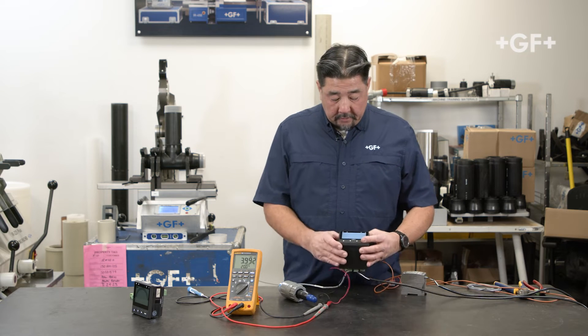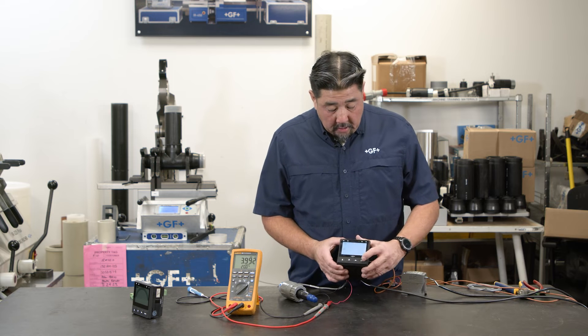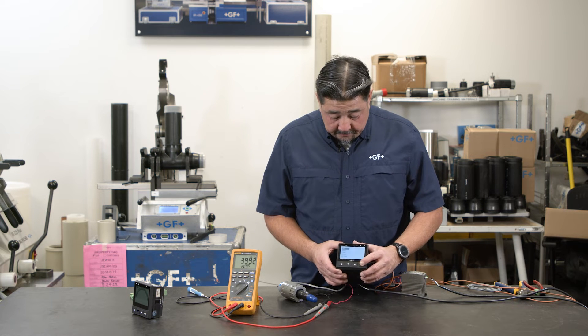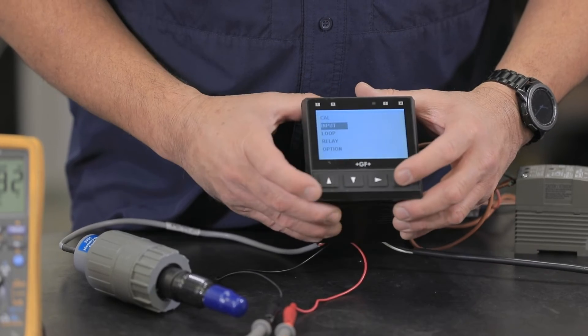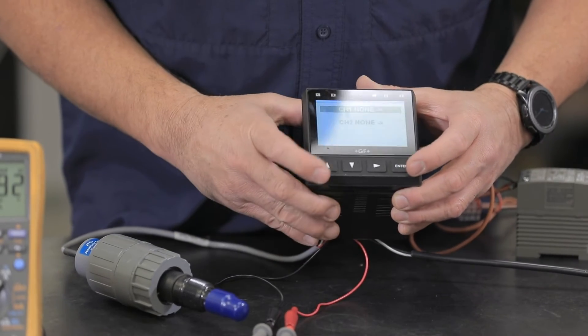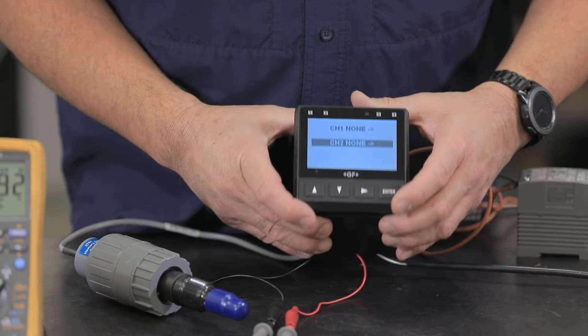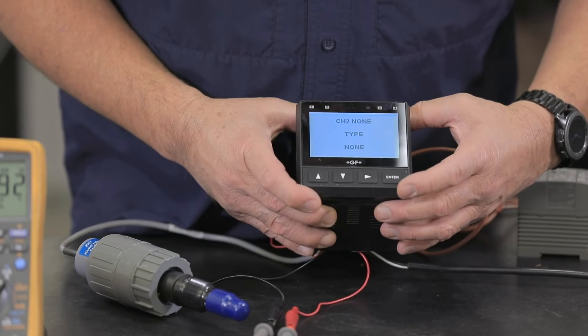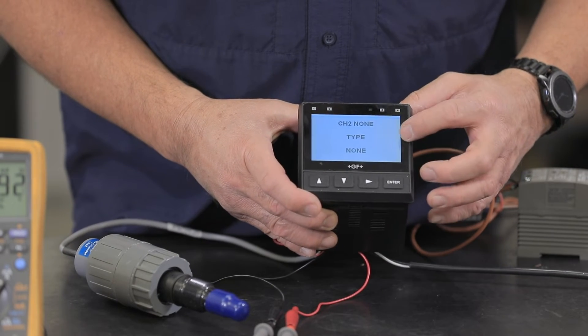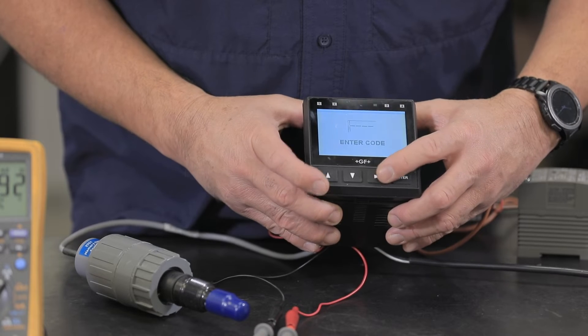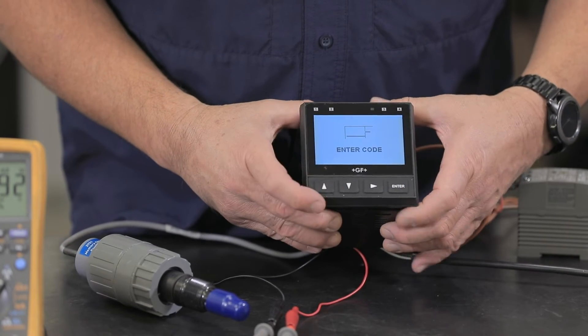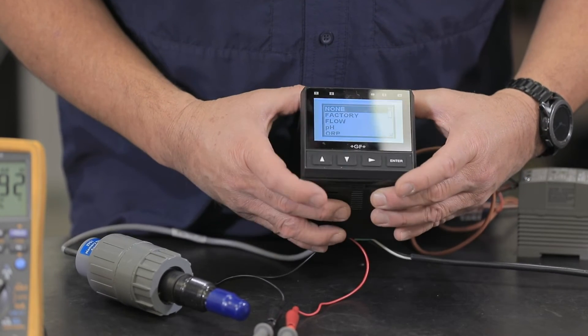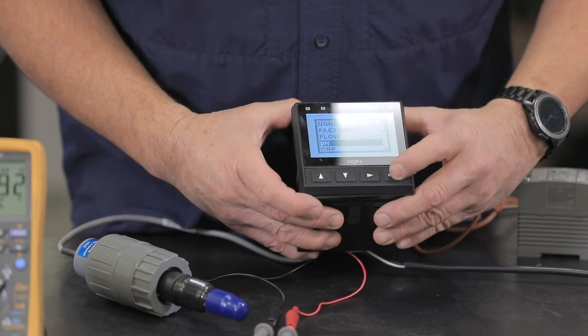So let's go ahead and configure the 9950 to accept pH. Press and hold the enter button, arrow down to input and press enter. I need to do channel two, so I'll hit channel two and the right arrow button. Channel two type none, so we're going to hit the right arrow. Enter the code which is up, up, up, down, and we'll choose pH. Enter.